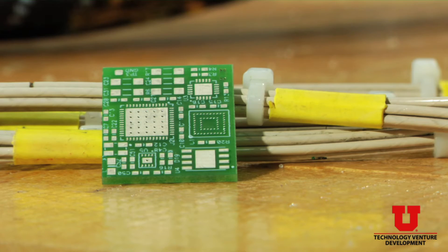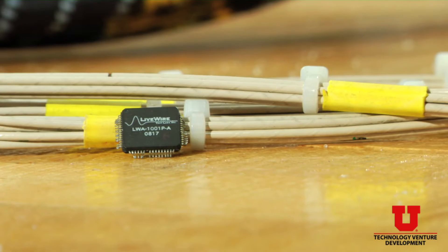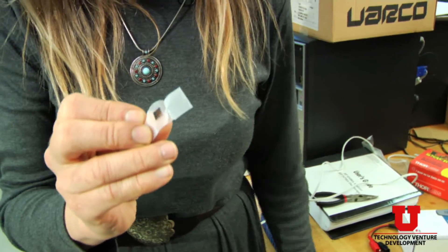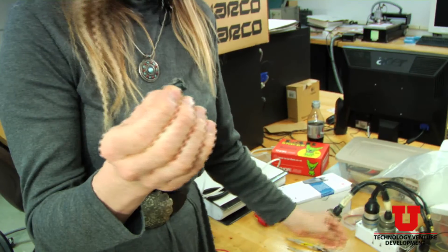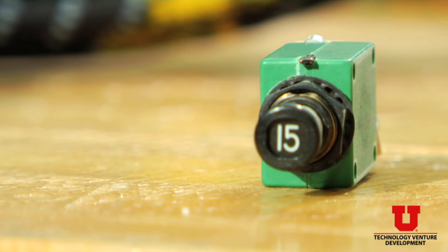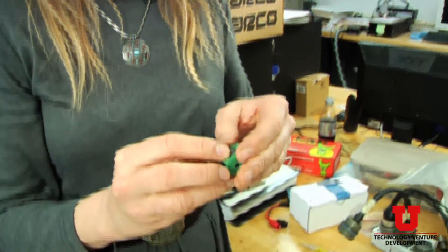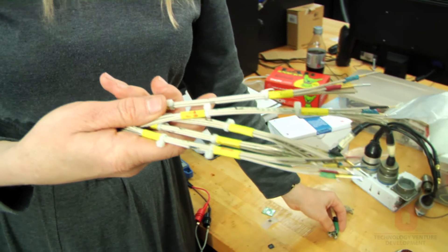It was a game changer. The fact that you could test the wires while the plane was live and flying was amazing. That's a chip, packaged like this so the silicon is inside, and you could put this chip inside an arc fault circuit breaker so that when the circuit breaker tripped, this would also locate the fault. It sends the signal down the wire, it can tell where the fault is, and it can do that in less than a millisecond — so it's able to both locate and detect these kinds of really tiny faults.